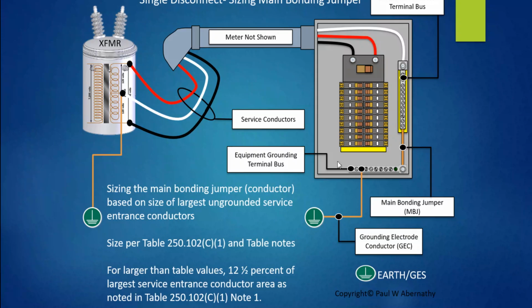Since this is the more complicated application, where I separate these two buses out to keep you thinking, here's our transformer. It comes down, no meter shown for simplicity of the graphic, and it comes in, so we have our grounded conductor here. In this case it is going to be a neutral because of the configuration, and because it is connected to earth, it is truly a grounded conductor. It comes over here, and now I've got the bus over here, since I didn't have enough room, let's say, over here for all the grounded conductors and equipment grounded conductors. So I added a separate bus. This bus is bonded to this enclosure by a factory kit. Now I need to connect these two together with a main bonding jumper of the wire type, so I have to size it.